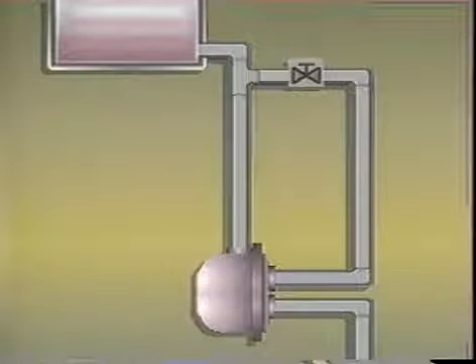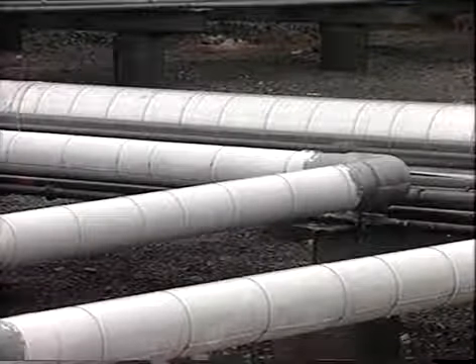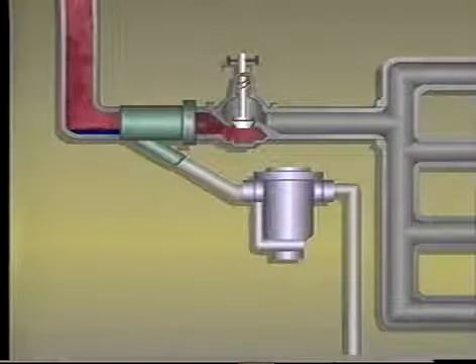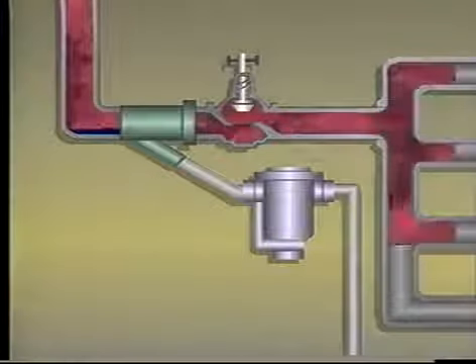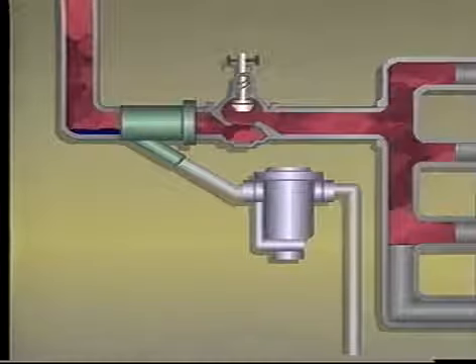To control differential shock, you must prevent condensate seals from forming in biphase systems. Condensate lines must be sized correctly, and long vertical drops to the traps must be backvented. The length of the lines to traps should be minimized, and the lines may have to be insulated to reduce condensing. The installation of a proper drip leg ahead of control valves will prevent differential shock from occurring when the control valve is opened after a period of closure. Careful attention to these few guidelines will prevent most water hammer.